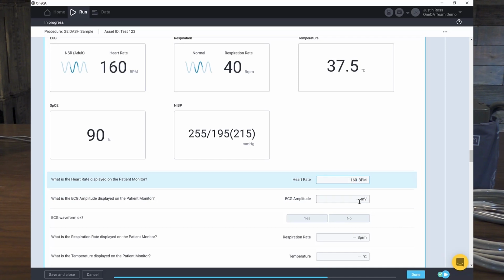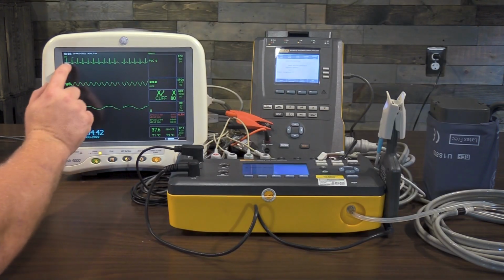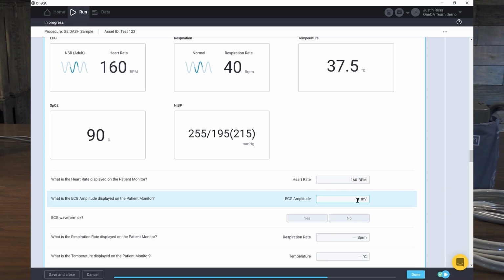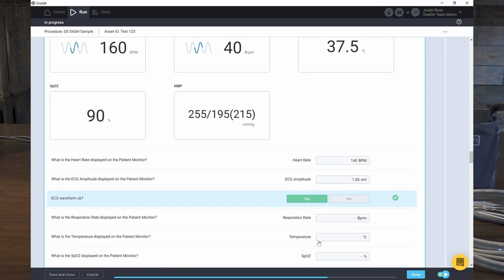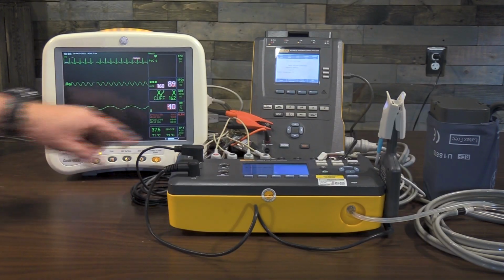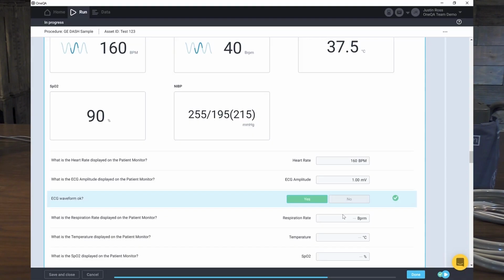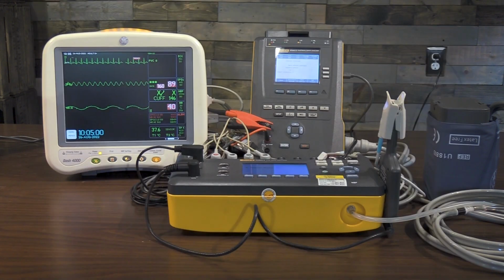All right, my ECG amplitude is displayed as 1 millivolt right there. Good. My waveform looks pretty good, so we'll mark yes. My respiration rate is supposed to be 40. We're reading 40. It's right on the line, so we'll put 40 in there. The temperature is supposed to be 37.5. We're reading 37.6.